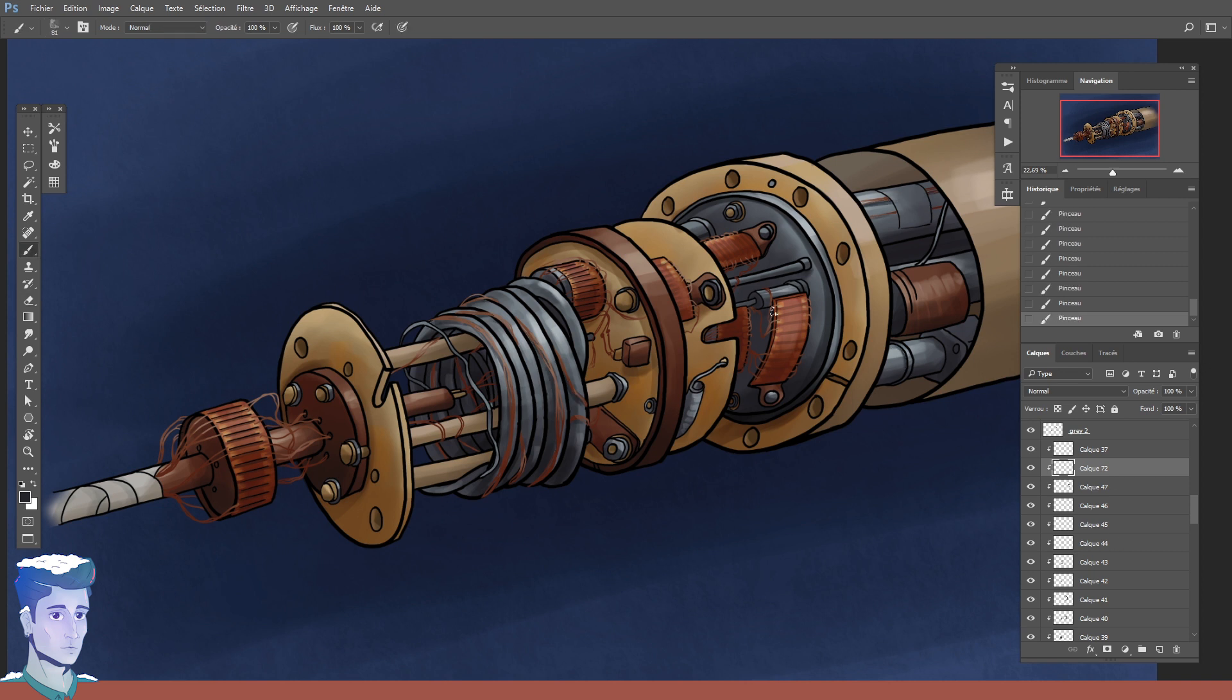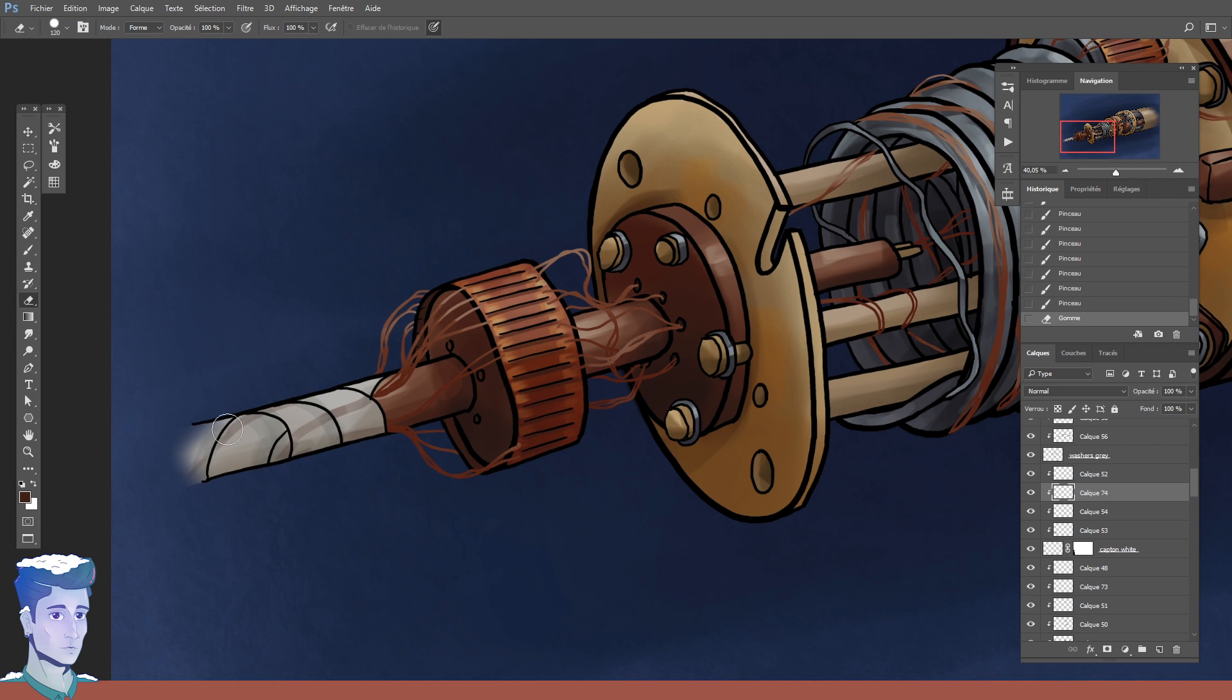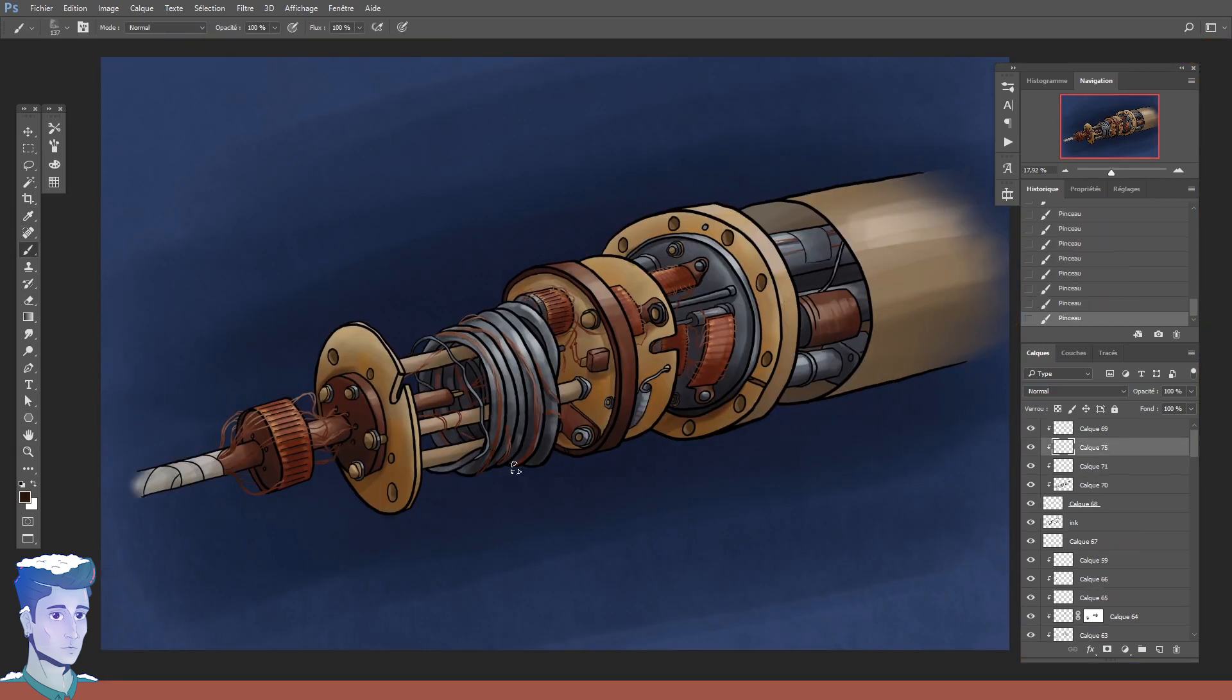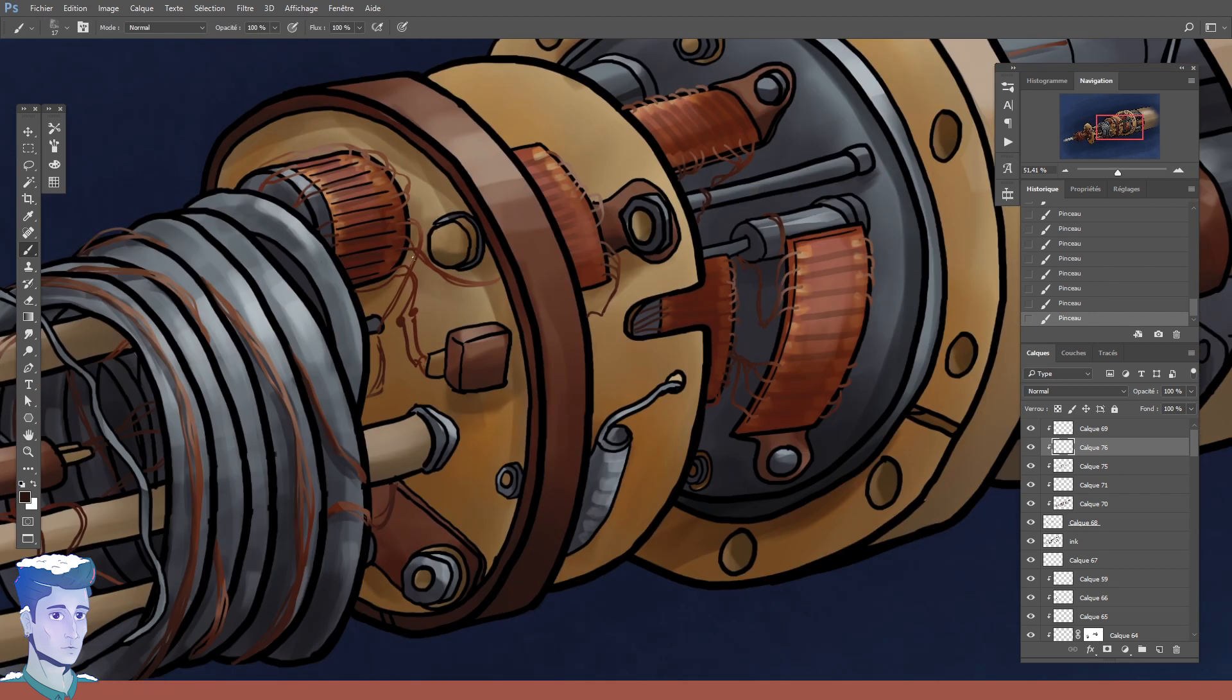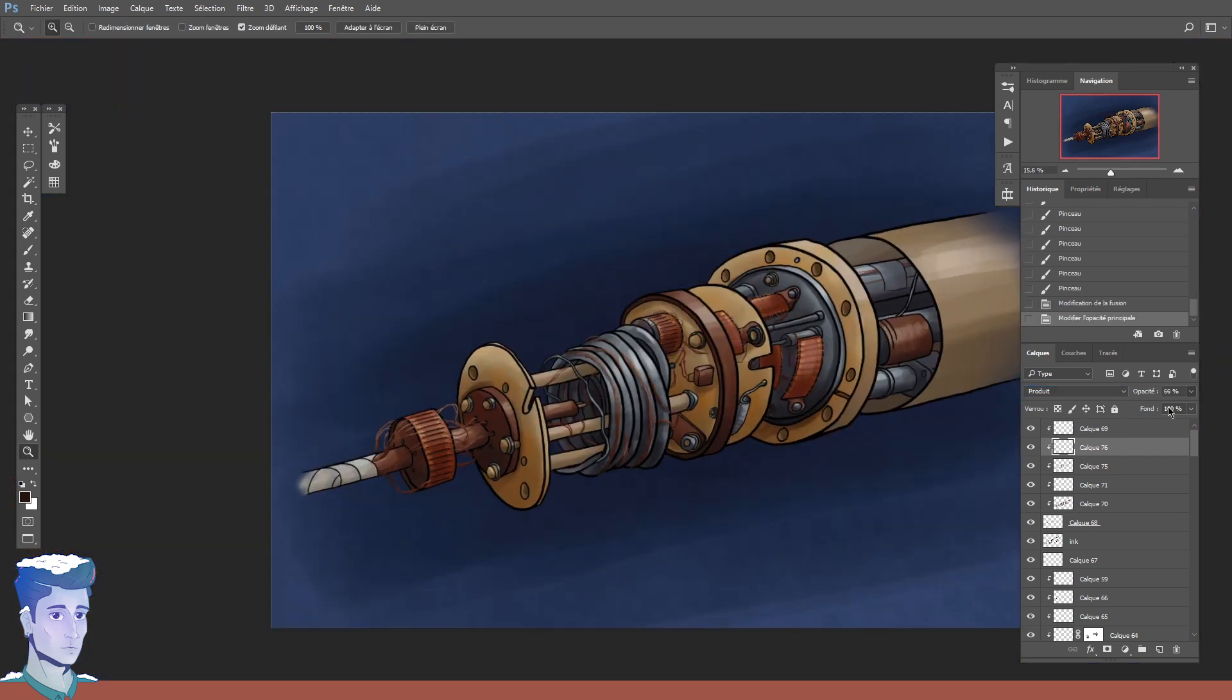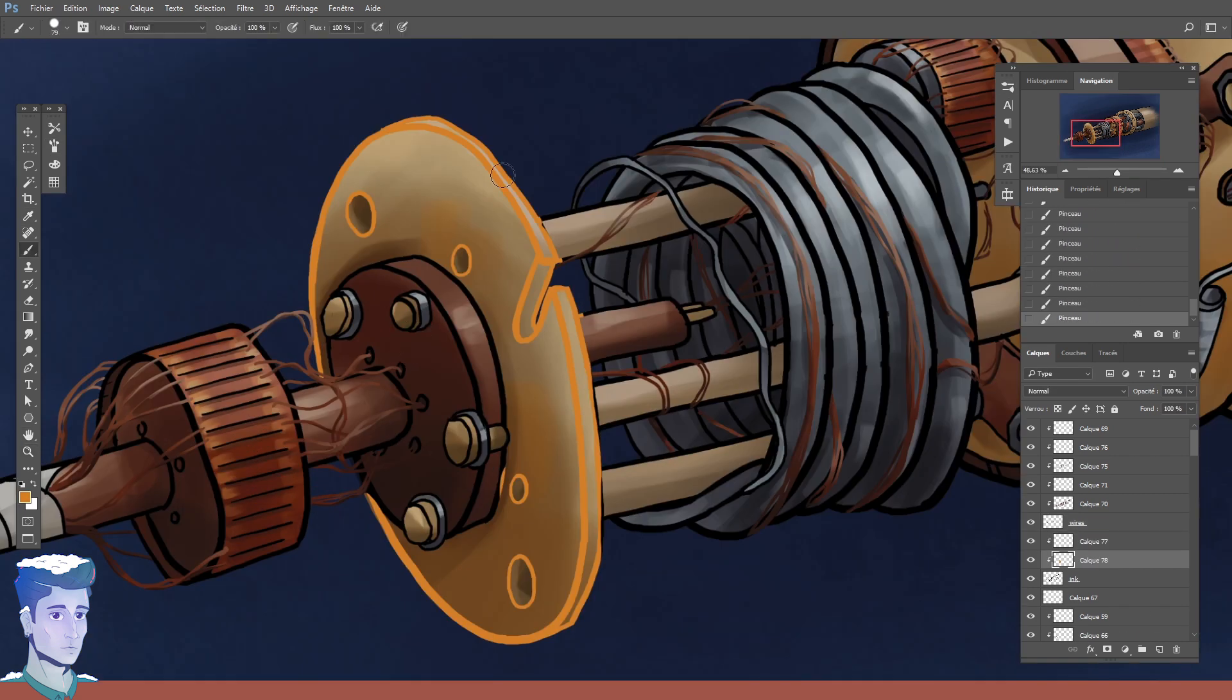This is the leftmost gold-colored stage in this drawing. By pumping on the helium mixture, a part of the helium will evaporate in the still, which will force the helium to go through the exchanger from the mixing chamber. In that chamber, replacing the evaporated helium by new atoms will need heat to occur, and so the mixing chamber will absorb the heat from the rest of the setup, therefore cooling it.